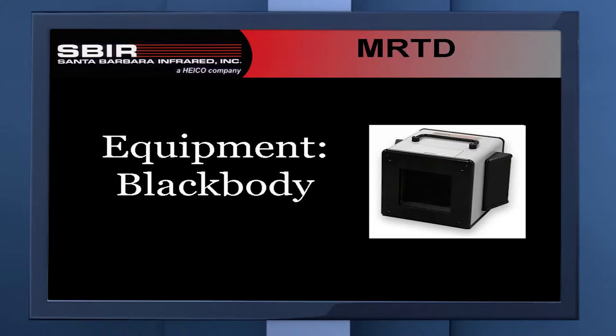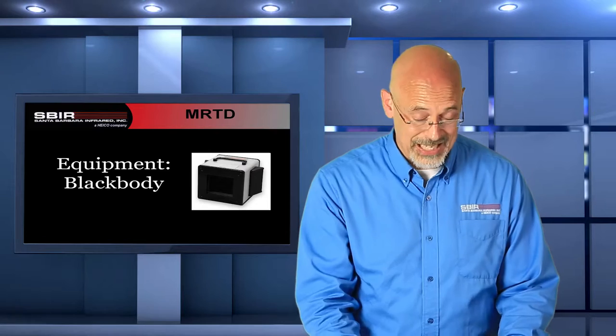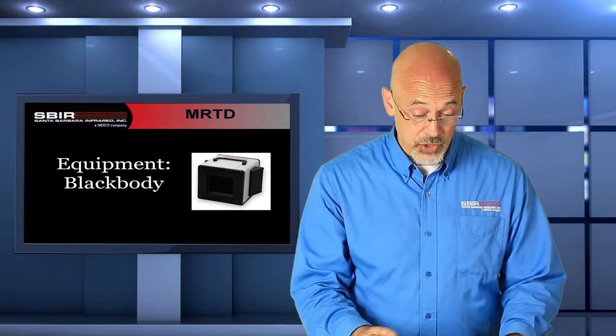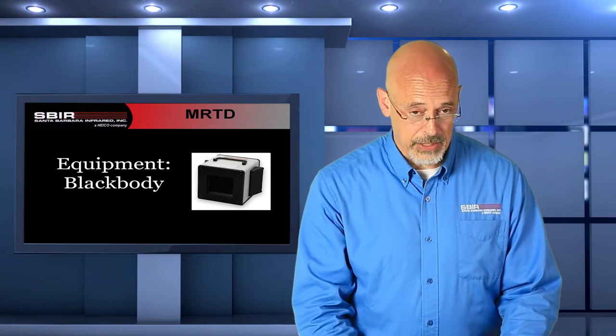What do we need to run the test? Well, traditional equipment. We need a blackbody. In this case, it's got to be calibrated. We're going to be taking very small measurements, and so it's important for us to be able to set that blackbody accurately.